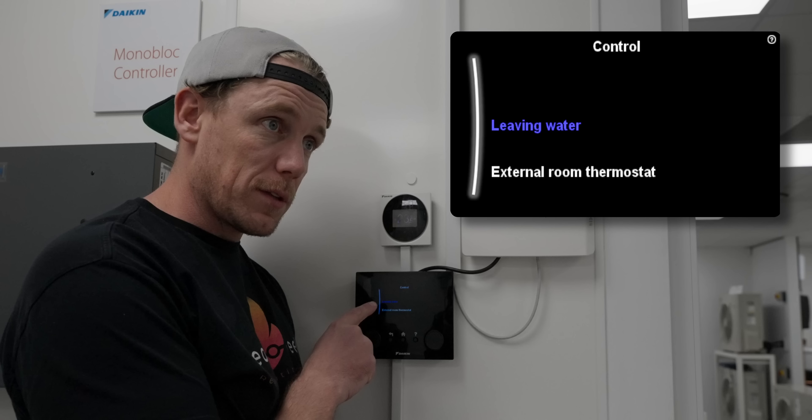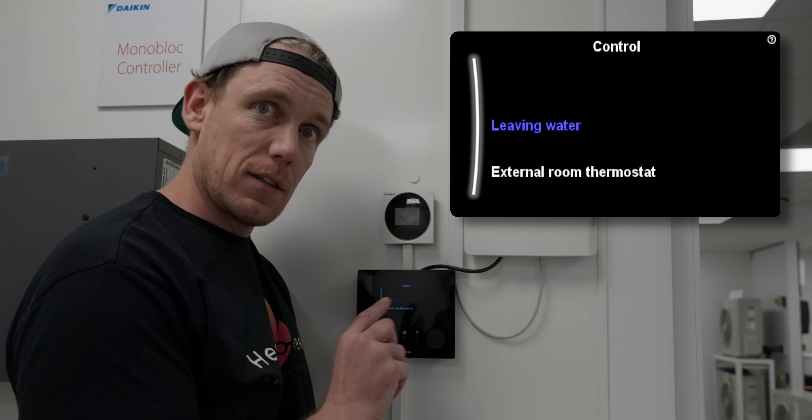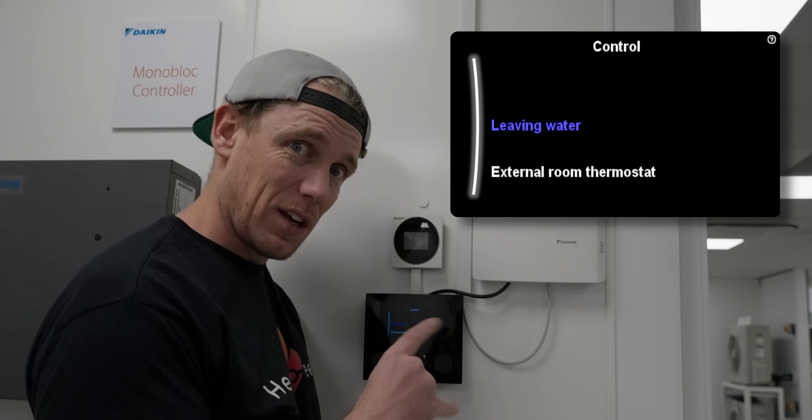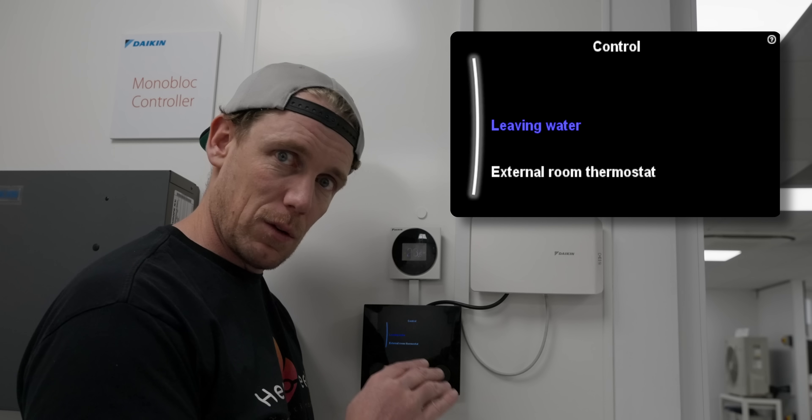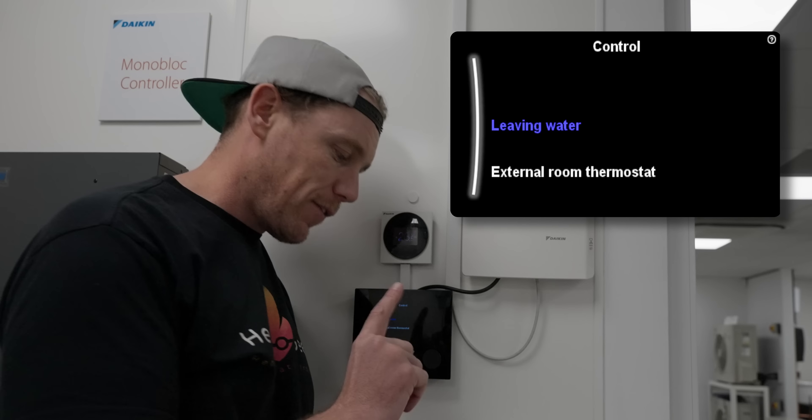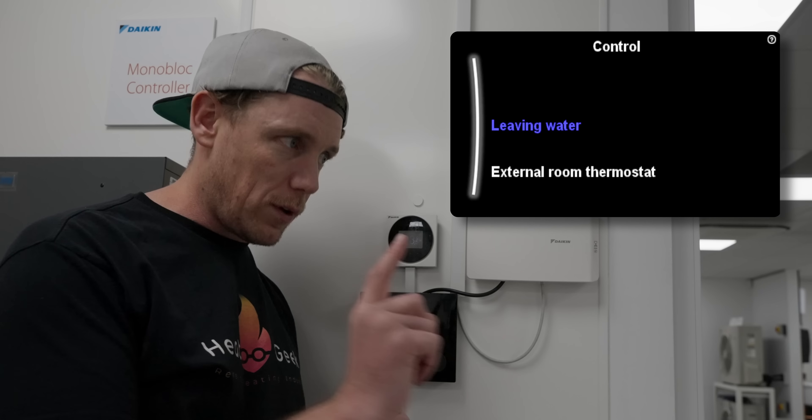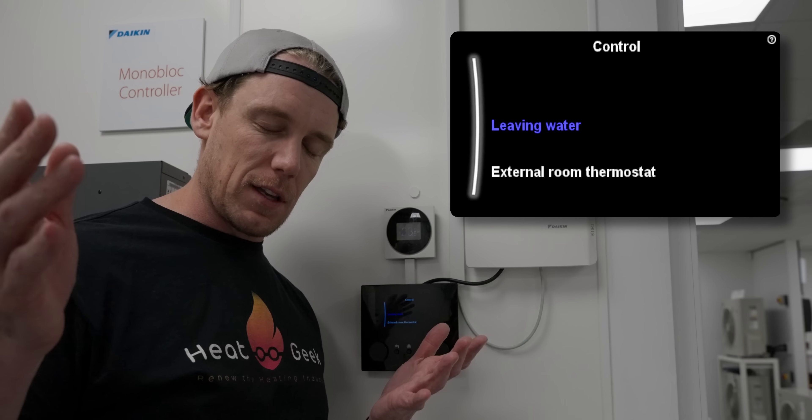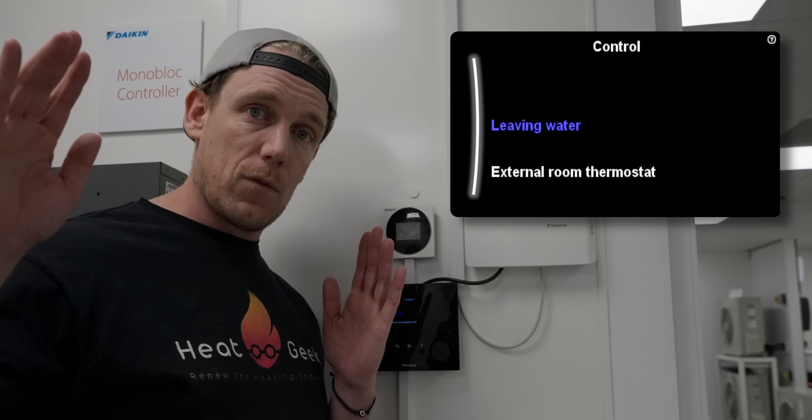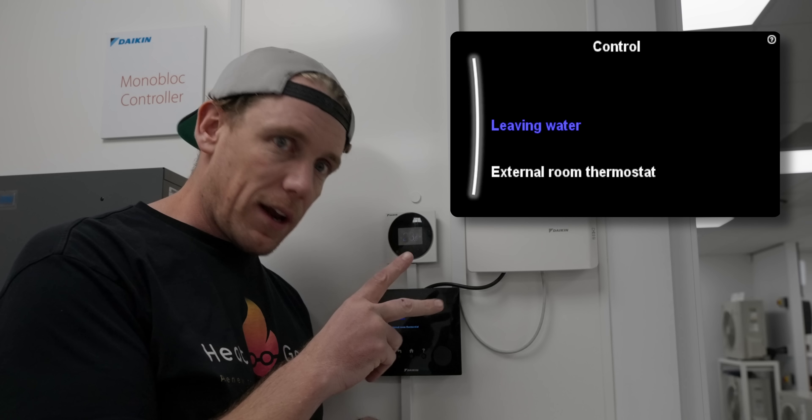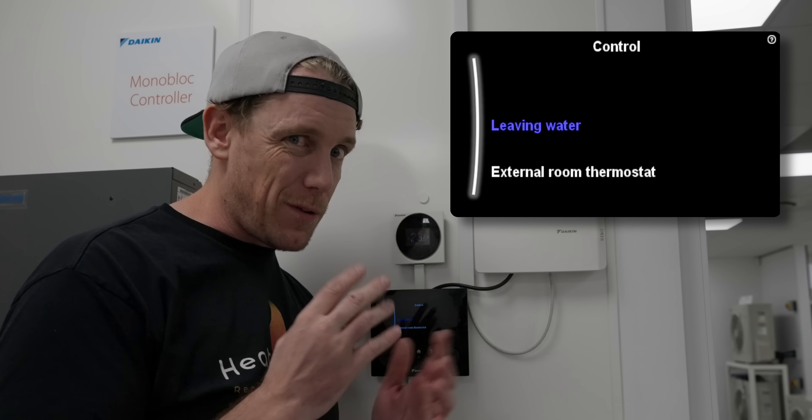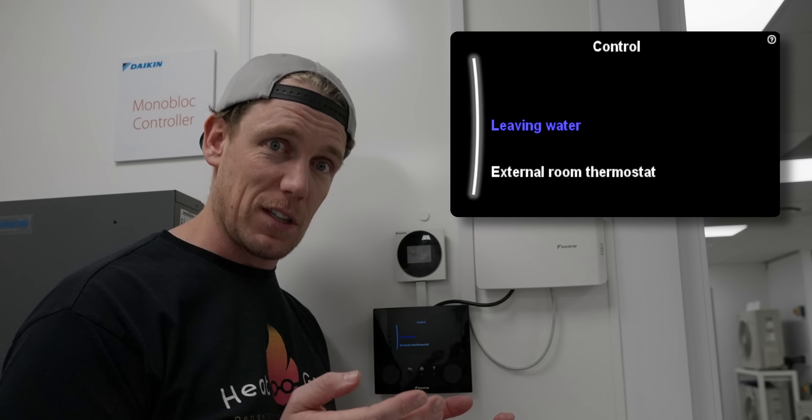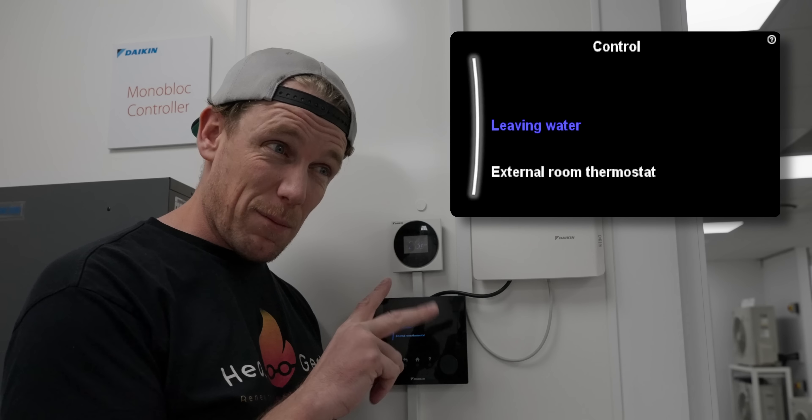Leaving water is fixed temperature flow. This will be pure weather compensation. Daikin do pure weather compensation. You're going to have to play around with that curve and really tune it in quite accurately to get it to work nicely. Having said that, if you've got underfloor heating with thermostat in each room, you can set all your thermostats to say 30, play around with your curve throughout the whole year. This is for more geeky homeowners or installers that are going to spend a lot of time getting maximum efficiency. Most people won't do that.